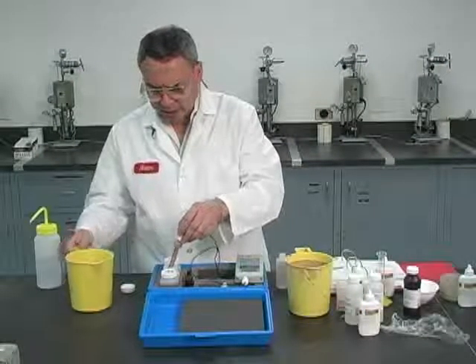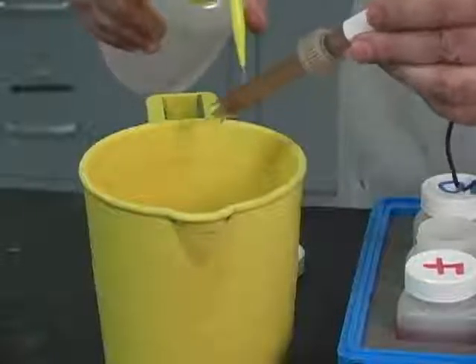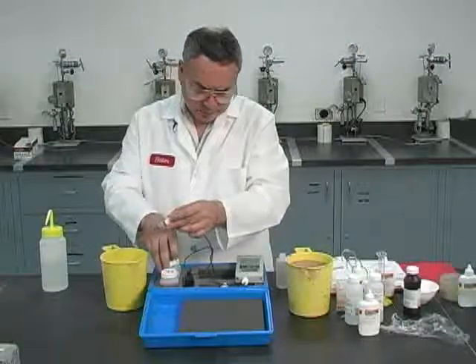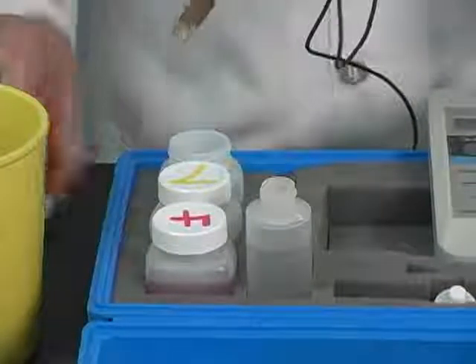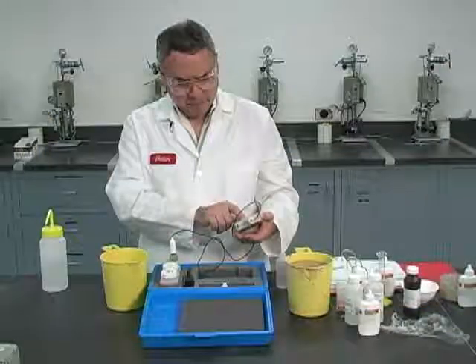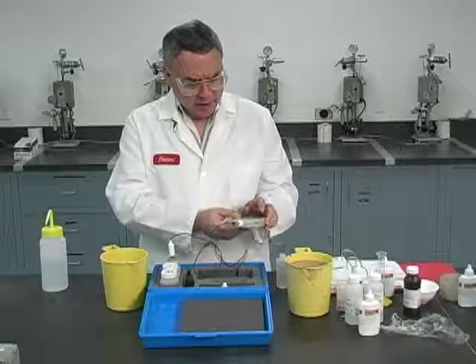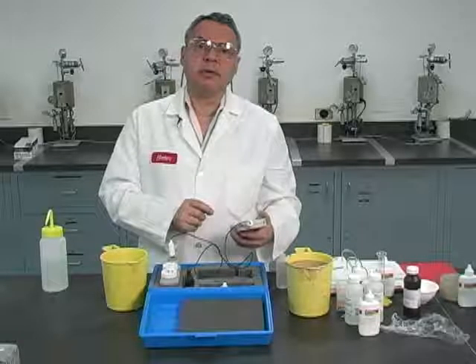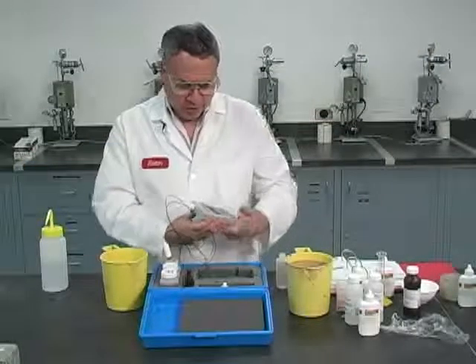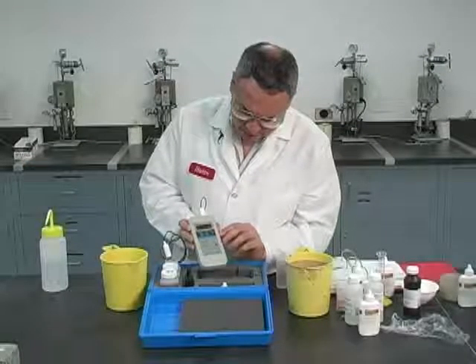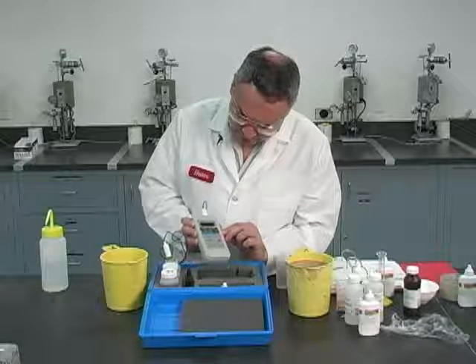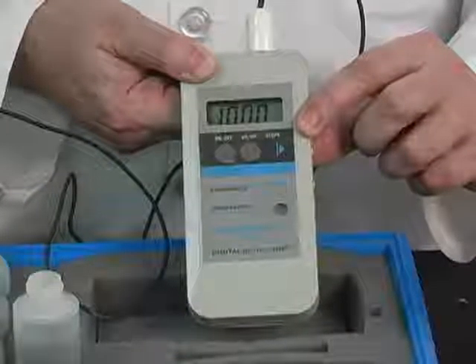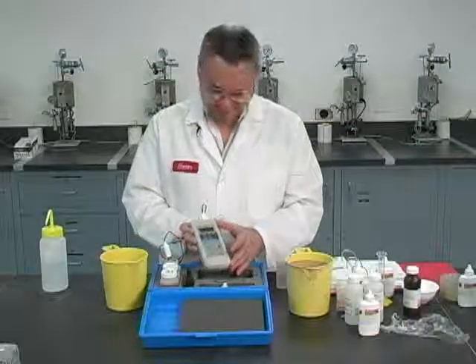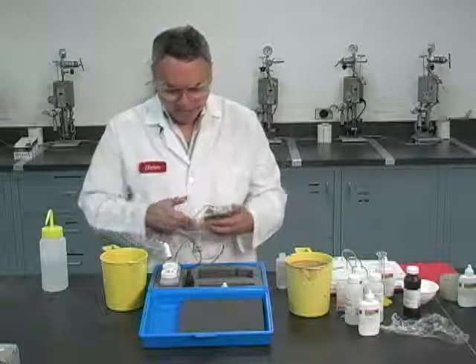Once I've done that, I can move now to the next buffer. I'm going to go ahead and quickly remove this, rinse it carefully, cover the buffer solution, and go to the buffer that has a pH of 10. Temperature is the same. And now I have to correct another screw which is labeled as slope. Right now it's reading 9.94. So what I'm going to do is correct it until it reads 10. And here we got a 10. So that would be the end of the calibration.